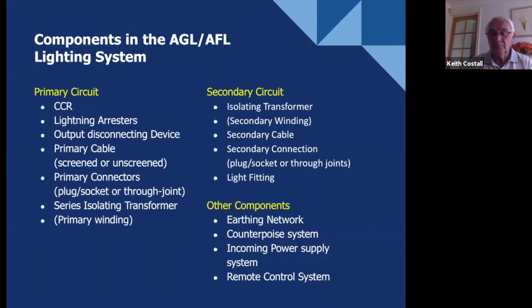Other components in the system, though, is an earthing network. So we do actually put a common reference around the system in the form of an earthing network. But we also have something called a counterpoise system. Now, a counterpoise system is an earthing network, but it's an earthing network that is dedicated for lightning protection. It is separated in installation from the primary cable, so that if there is an indirect lightning strike, this bare copper counterpoise cable will attract the lightning, the electrical charge, and safeguard the cable. That's the idea of it.